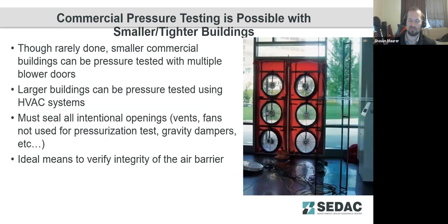And it is a technology that can be applied to commercial buildings. As we've improved commercial materials and air tightness, it's more and more possible now to use blower door testing for larger and larger buildings. Although if you have a very large building, setting up a blower door like this one might not be able to do enough depressurization for the test. It's possible to set up the HVAC systems with a little bit of preparation, such as blocking off the exhaust fans and taping off some outside air damper openings, to then turn on the supply fans and use those to draw in air and pressurize the building. It's a good way to run that test. You can measure the airflow off those air handlers with the already installed BAS system, and that will give you an idea of what your building's leakage rate is.